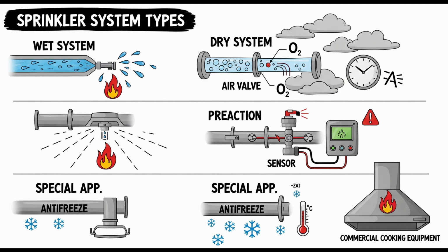Clever. Correct. Any water that gets into that small section, whether from condensation, a test, or minor valve leakage, drains back into the main dry pipe or stays in the heated area where it won't freeze. Okay. What's the other option? The other permitted scenario for pendant or sidewall sprinklers is if the sprinkler and branch line are in an area above 40 degrees Fahrenheit, the water supply is potable, and the piping used is either copper or CPVC that is specifically listed for dry pipe applications. Got it. Copper or CPVC listed for dry pipe in a heated area with a potable supply. It seems like every single rule is designed to ensure no water sits stagnant in the cold pipes. That's the driving principle for dry systems.